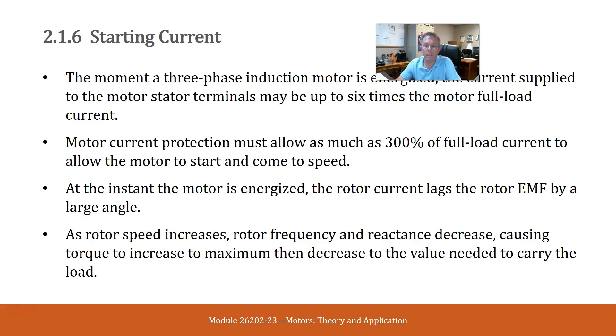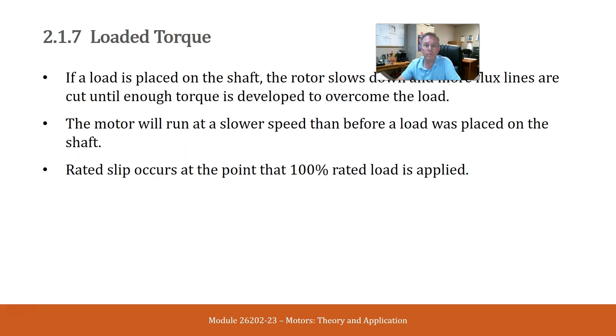At the instant the motor is energized, the rotor current lags the rotor EMF by a large angle. As rotor speed increases, rotor frequency and reactance decrease, causing torque to increase to a maximum, then decrease to the value needed to carry the load. If a load is placed on the shaft, the rotor slows down and more flux lines are cut until enough torque is developed to overcome the load. The motor will run at a lower speed than before a load was placed on the shaft. Rated slip occurs at the point that 100% rated load is applied.